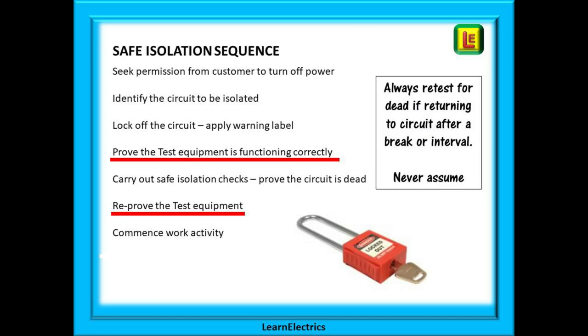There are established procedures for safe isolation that we should follow, and the method shown here is easy to apply. Seek permission from the customer to turn off the power. They may want to turn off the computer or washing machine before you start. Identify the circuit to be isolated. Turn the MCB off. Did the lights go off? If that is the circuit that you are about to work on, then that is correct. Lock off the circuit and apply a warning label. Prove the test equipment is functioning correctly. Carry out the safe isolation checks correctly and prove the circuit is dead. Reprove the test equipment. This is very important and a definite fail if you do not do this during an assessment. And then begin the work activity.